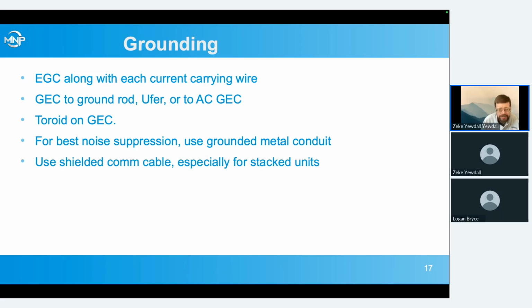We've seen people just using thermostat wire or something and running it in the gutter along with the AC wires and having a lot of issues, because if those stacked units can't very effectively communicate with each other, they can have a lot of errors, because they really need to know what all the other inverters in that stack are doing at all times to coordinate themselves.